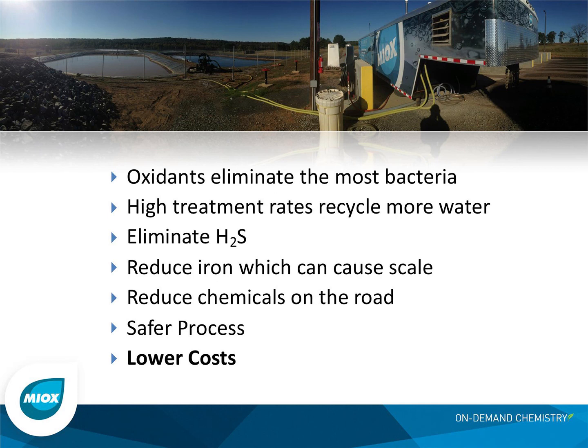Yeah, the field data has corroborated a lot of what we've seen with our lab testing. The only way we can do controlled testing is in the laboratory. And what we see there is that mixed oxidant solution tends to give better kills at the same dose and at the same contact time at higher pHs, all the way up to 9.5.